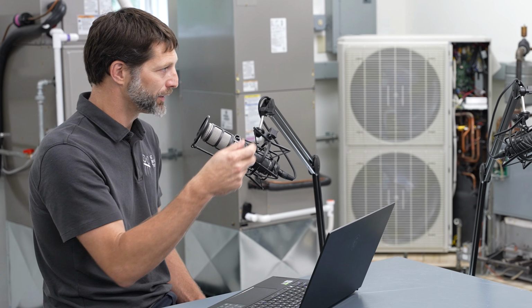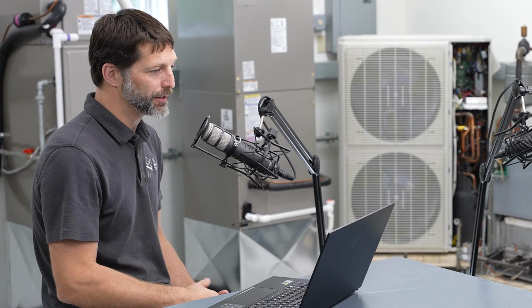Yeah. A lot of times it's a clogged strainer right at the inlet, or it could just be the pin is clogged with gunk. And that could have been from maybe somebody not flowing nitrogen while brazing. There's a lot of reasons why a TXV might fail, but a lot of times it's due to outside circumstances. And of course, the older TXVs had the steel heads, and they would rust and potentially leak refrigerant out, which would then mean you wouldn't have the opening force. But the newer TXVs, they're not like that. A lot of times they're stainless steel, and so you don't have that problem. And so it's usually from outside circumstances.